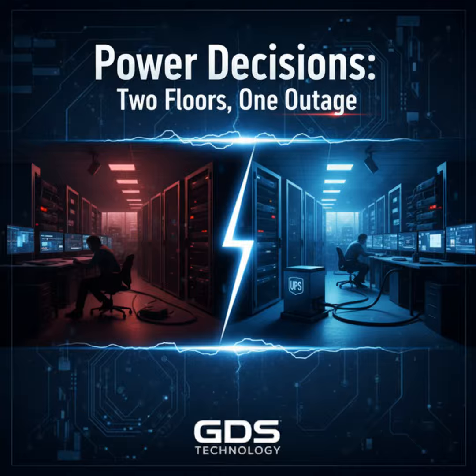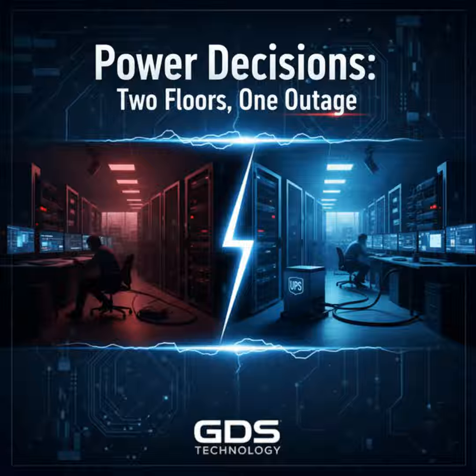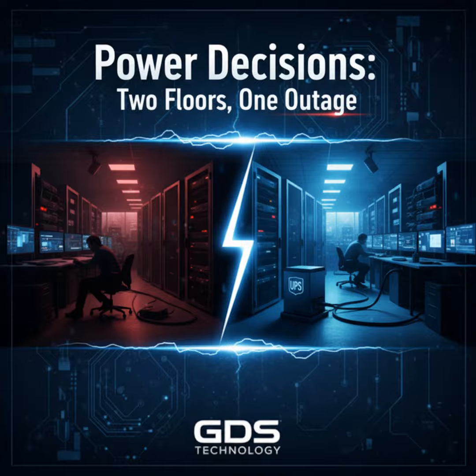Floor 2, on the other hand, went a different route. Modestly sized UPS capacity covering the defined critical loads, explicit written ownership for each piece of equipment, and a simple documented test that was executed quarterly. The outage still happened, but the handover steps and the UPS gave staff the breathing room to restore services in under 30 minutes.